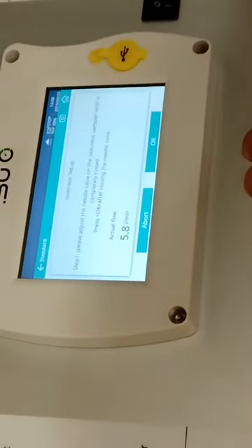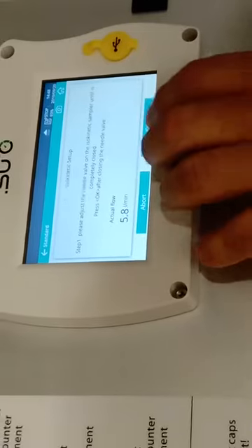We need to achieve a certain flow here. That is fixed by pressure and the leakage produced. Please adjust the needle valve. This must be completely closed. Now it's closed. If you get a stable reading here, then you press OK. Let's see, that's stable, 5.8.